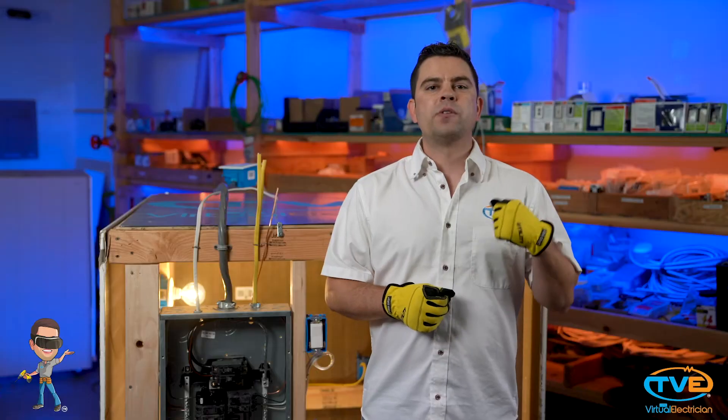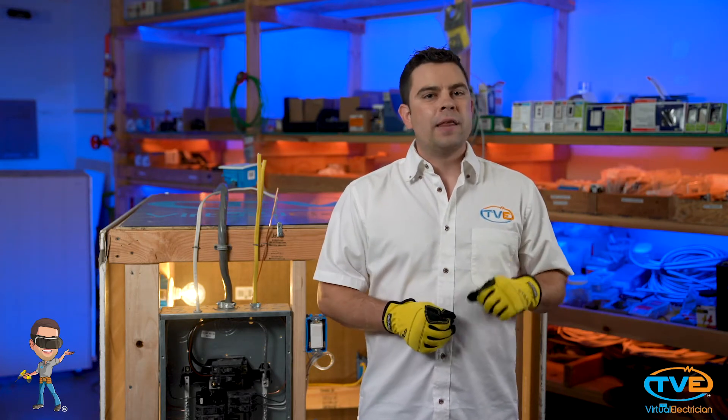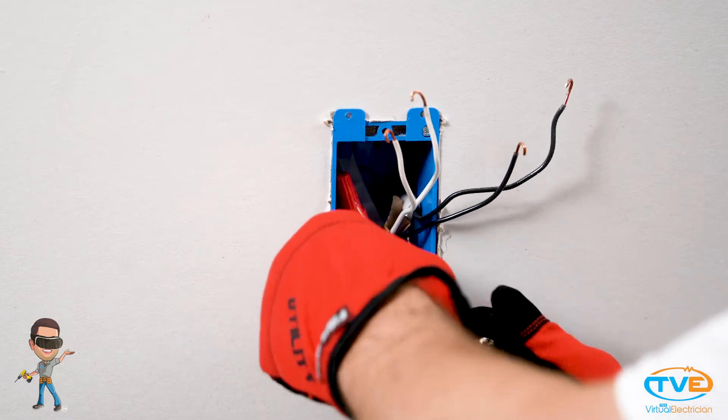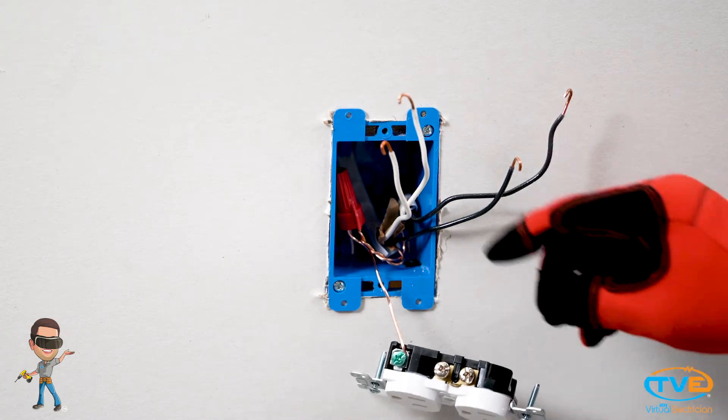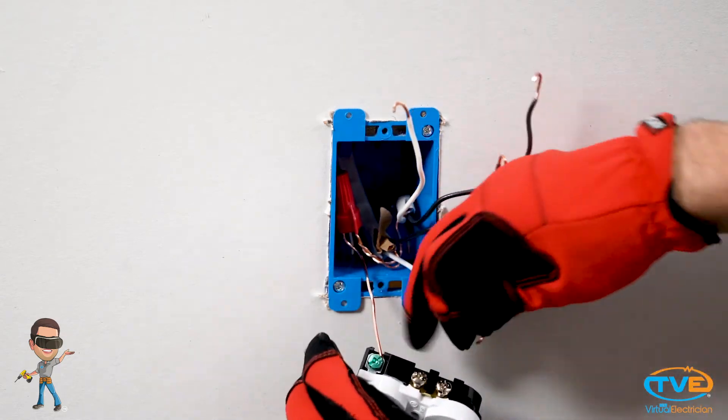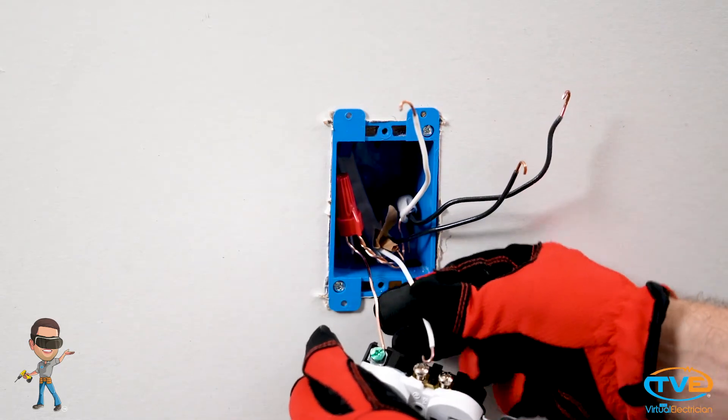For best practices, always make sure you wire the ground wire first, then the neutral, then the hot. Always put the loop on the screw the same direction the screw will tighten down clockwise. If you don't, you'll be fighting against yourself and may cause a loose connection.